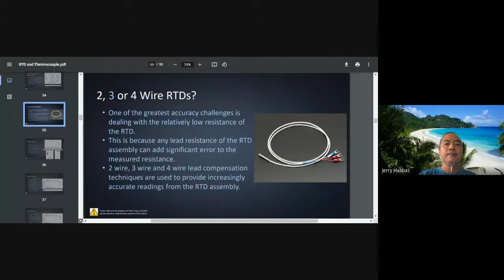Okay, so we'll start with 2 wires. Notice that there's RL1 and RL2. RL1 means the extension wiring of your RTD, which could generate resistance as well. So that's why RL1 is the resistance of the lead wire. So therefore, at the output terminal, you'll be expecting the summation of the total resistance, including your RTD's resistance. So there will be a problem if R1 or R2, or RL1 or RL2, gets affected, okay?